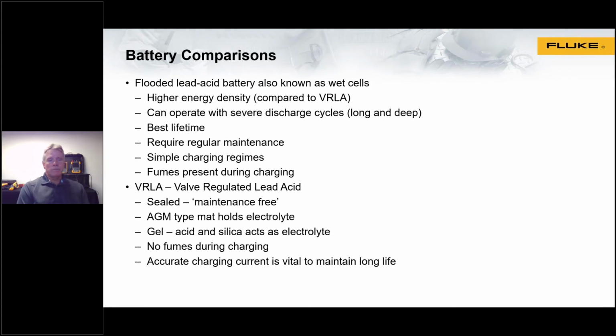So let's take a quick look a little bit deeper, comparing the VRLAs versus the flooded lead acid batteries. The flooded lead acid batteries, they do have a higher energy density, so that would be a positive. They can also operate pretty well with some severe discharge cycles, so they really give you the best overall lifetime. They do require regular maintenance, and part of that maintenance really is making sure that they have battery electrolyte. And also, kind of a downside, fumes can be present during charging.